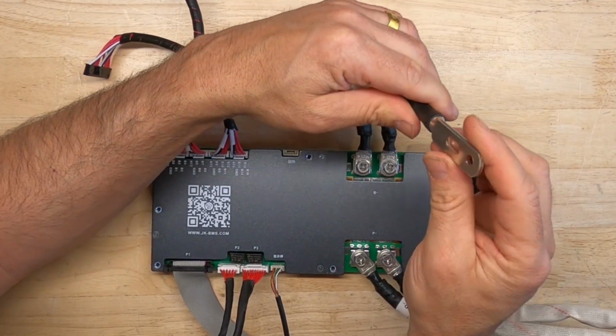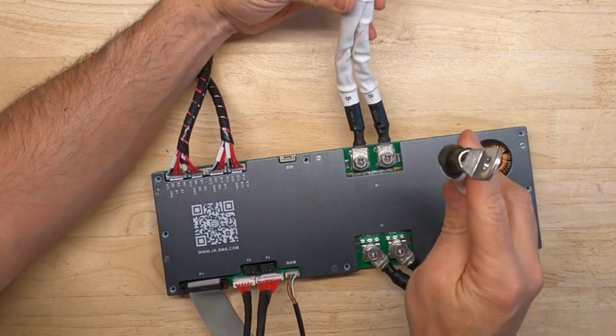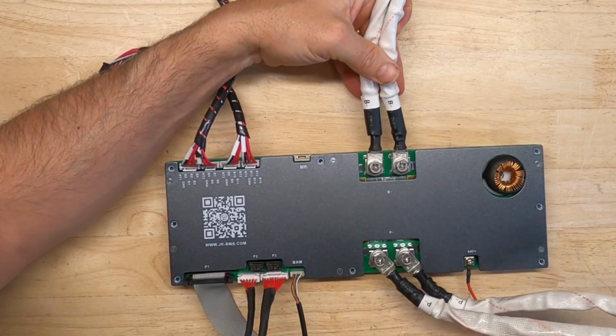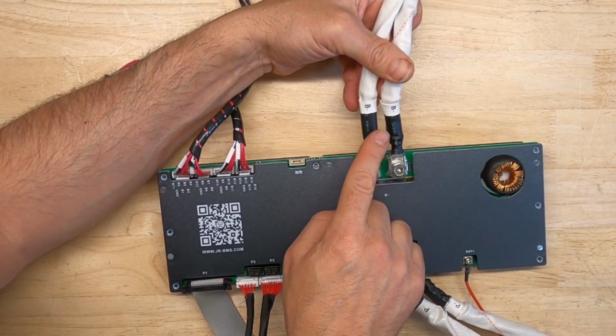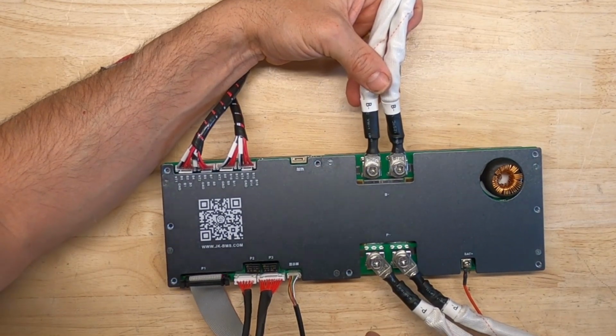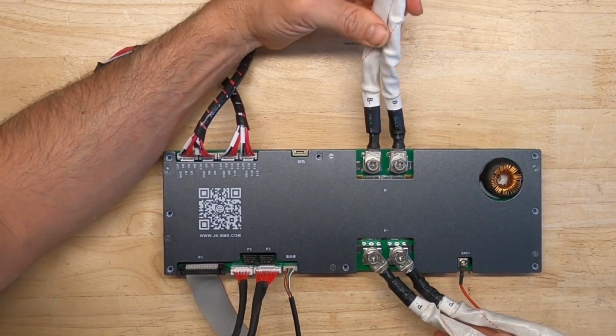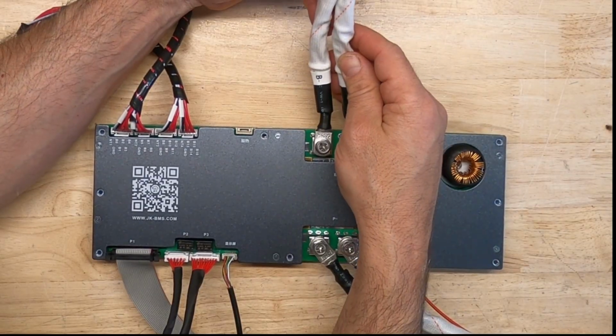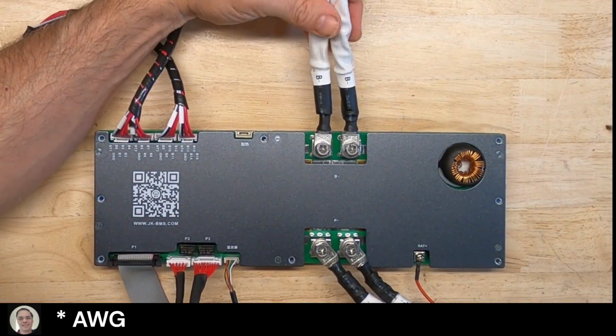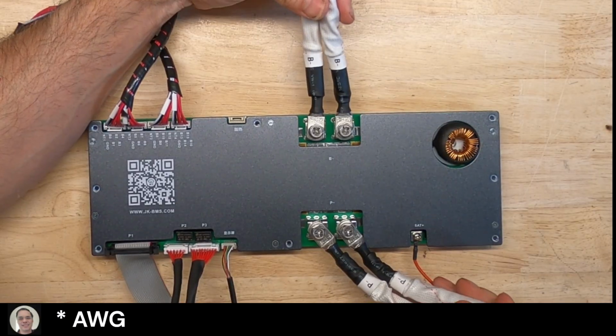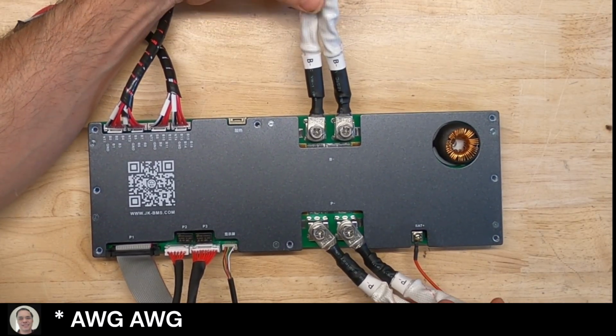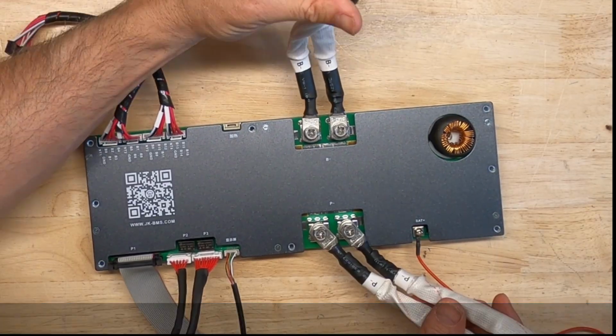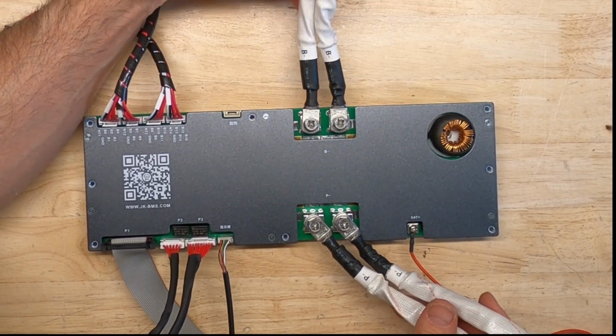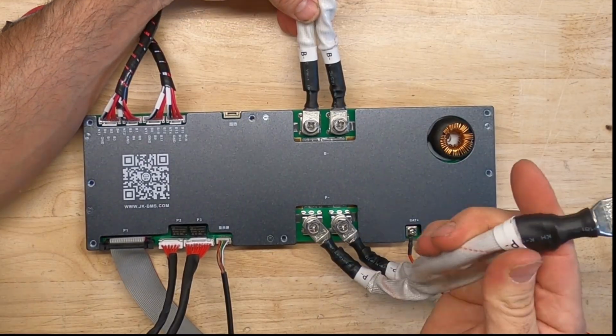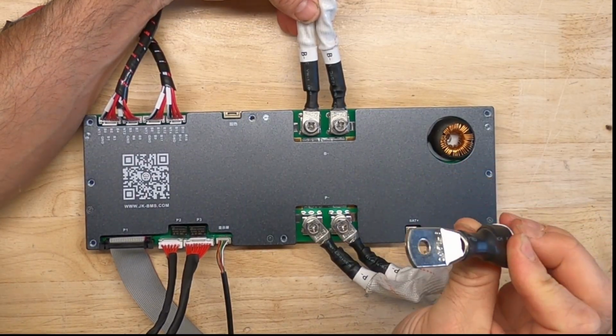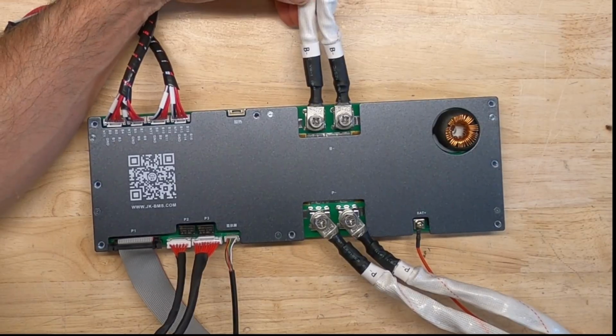These lugs definitely seem sufficient for 200 amps, so I'm really curious now. These are 125 degrees Celsius insulated, just like the cables on the version 1 box. I don't know what size they are, but they're doubled up, it could be 4/0. If that's the case, if they are 4/0 times 2, then technically with this insulation it may be able to... we may have to actually test these cables. They're not used in the boxes, so I don't know if it's even worth testing, but maybe if I'm bored I'll do it.